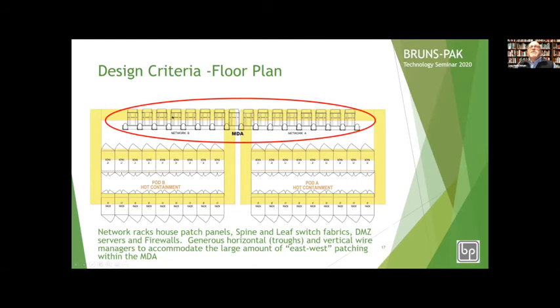The network racks house patch panels, spine and leaf switch fabrics, DMZ servers, and firewalls — with very generous troughs and horizontal cabling within four-post open racks, and very large wire managers going north and south. When you get into spine and leaf, where everything connects to everything, you get enormous east-west cabling — which is why there are troughs at the top, middle, and bottom of these racks. Generous horizontal troughs and vertical wire management should accommodate the large amount of east-west patching within the MDA.